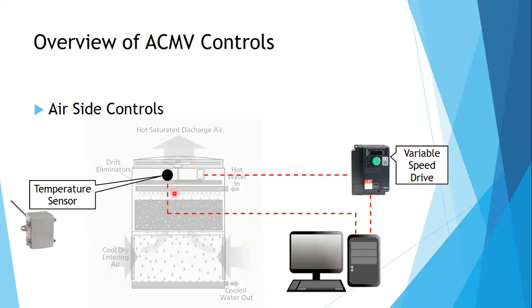For example, let's say your cooling tower manufacturer says the delta T is about 5 degrees Celsius, so 32 and 27. When the cold air comes in, hot air comes out. So it says 27 in and supposed to be 32 out. If the air temperature is less than 32, the variable speed drive will tell the motor, hey, you're working too hard, you can lower down a bit. You can slow down.